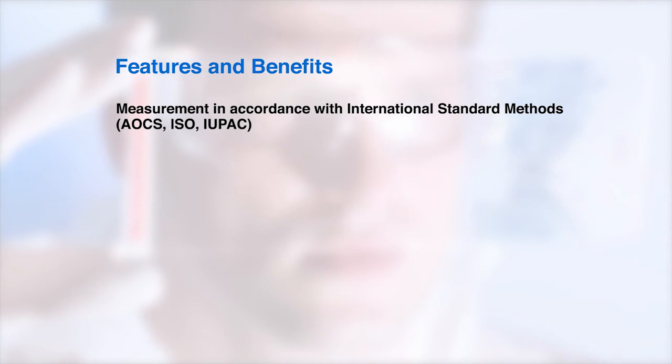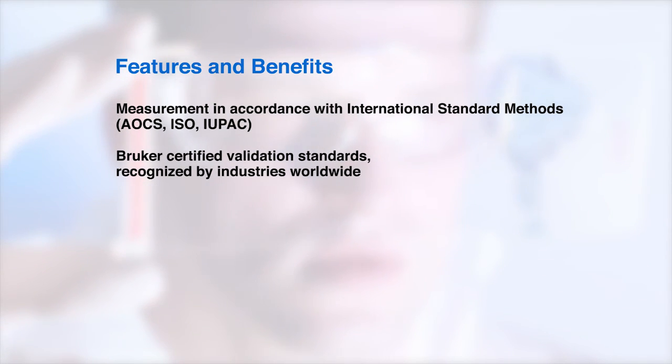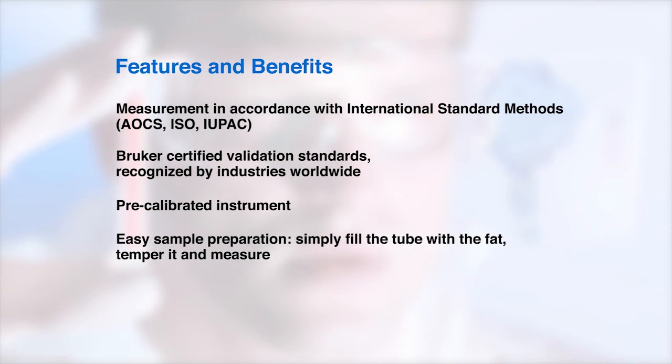Time domain nuclear magnetic resonance methods for solid fat content determination in fats and fat compositions are recognized as international standard methods. Bruker provides a set of three validation standards which are recognized worldwide as industry standards. The minispec is delivered pre-calibrated. Any type of fat can be analyzed with easy sample preparation.